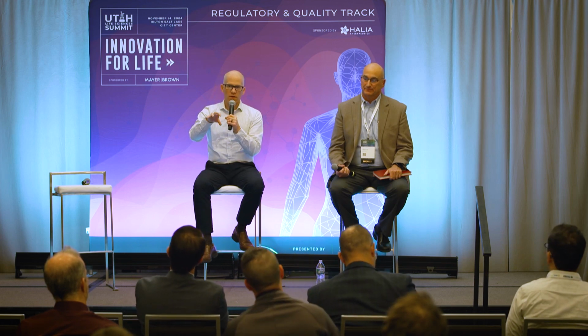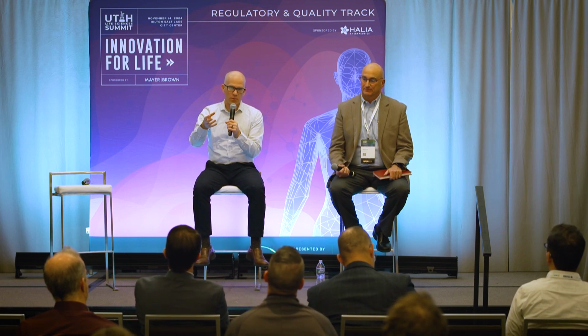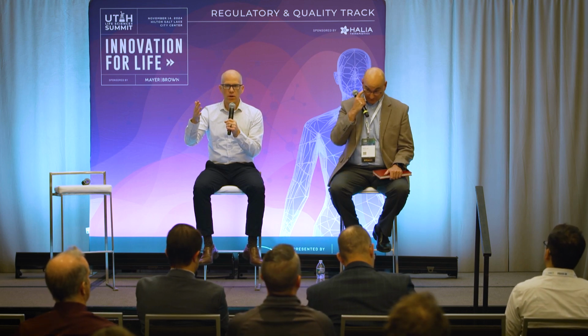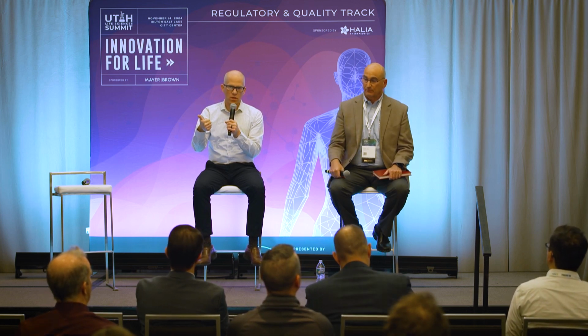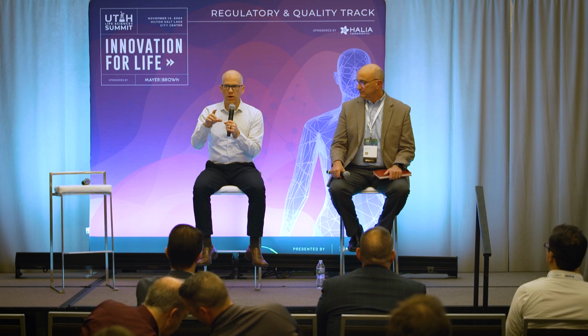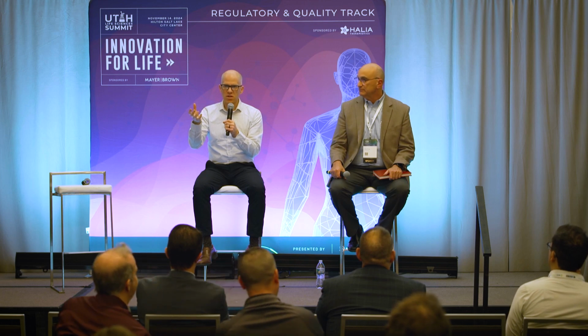So how often do you recommend revalidating or taking a look at the cybersecurity testing you did, given that the landscape is ever changing? Yeah, so that's another part of what the FDA wants to see, some sort of cybersecurity management plan. Depending on what you have, I generally recommend you rerun penetration testing once a year, and rescan your SBOM for vulnerabilities at some cadence. Along with that, every time we rerun penetration testing, I recommend re-reviewing your cybersecurity risk analysis to see if there's anything you've missed or need to add to it.